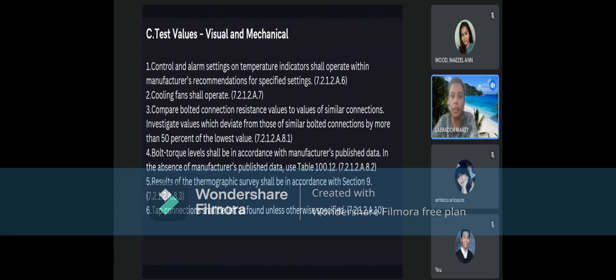Sa 3, compare bolted connection resistance values to values of similar connections. Investigate values which deviate from those of similar bolted connections by more than 50% of the lowest values. At dito, gagamit tayo ng low resistance ohmmeter according sa given test inspection. For number 4, bolt torque level shall be in accordance with manufacturer's published data. In the absence of manufacturer's published data, use table 100.12.